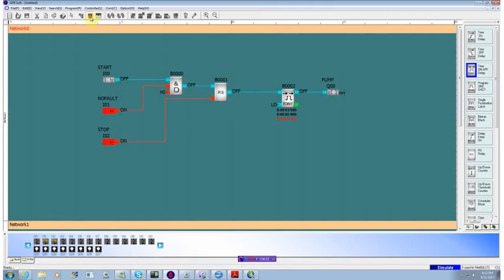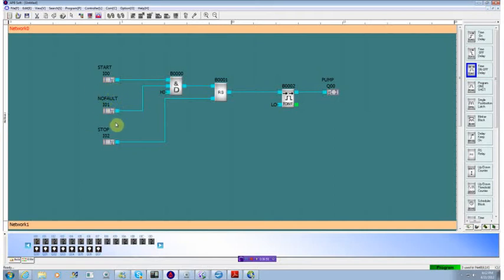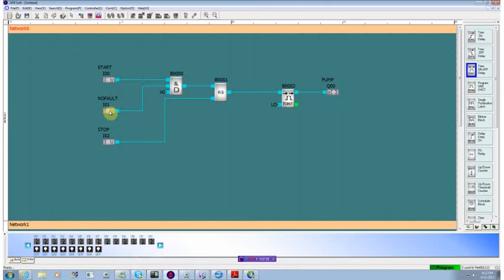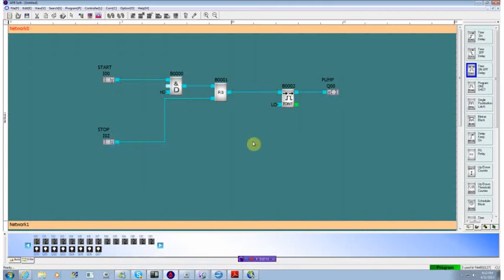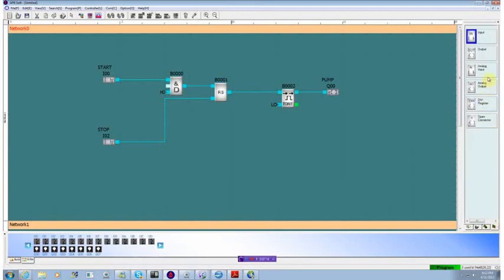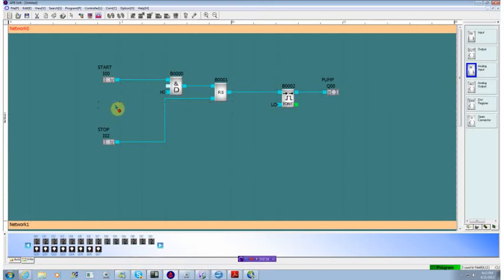And the last thing we want to do is change this fault handling. We said that this was a pump. We're going to assume that it's actually a submersible pump and that this is a seal detect input. Well, currently, it's a digital input that's coming in. We're going to delete that one. And we're going to go back to our I.O. types and see that we have an analog input.